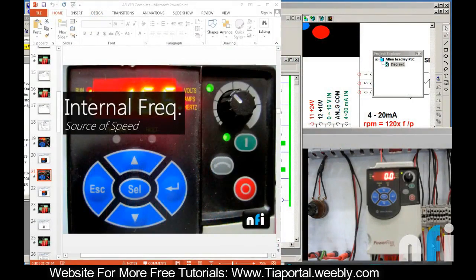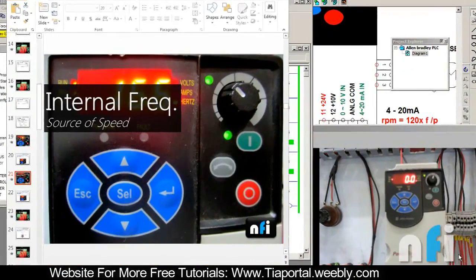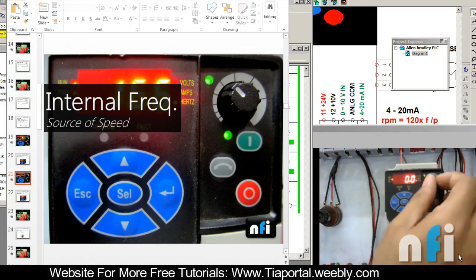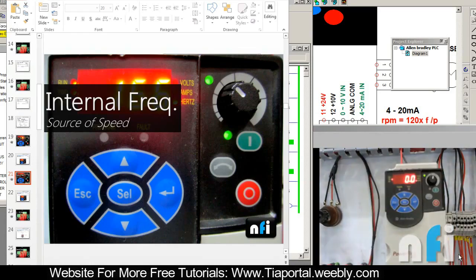There is one more option for controlling the speed of the drive, which is called internal frequency. Suppose you have just one fixed frequency which you don't want to change. If you're using a potentiometer and somebody changes the frequency, that may cause some effect in your program. To avoid that, this drive has a function where you can set an internal frequency, and whenever you start the drive it will run at that frequency only.